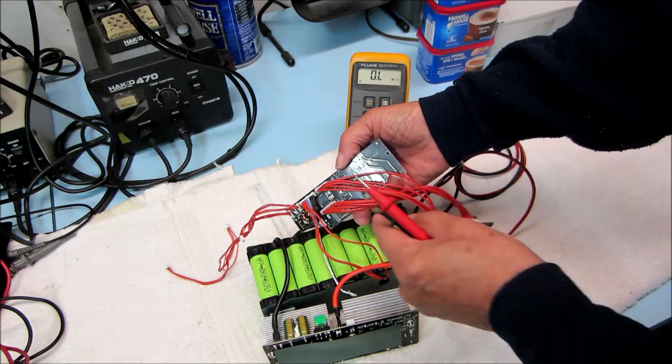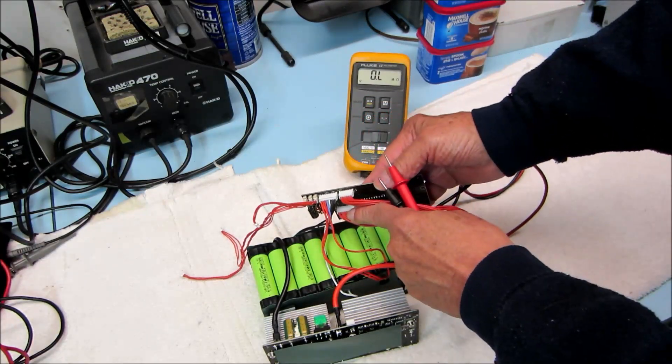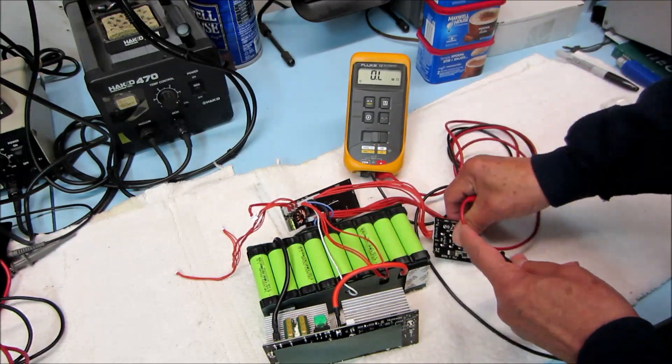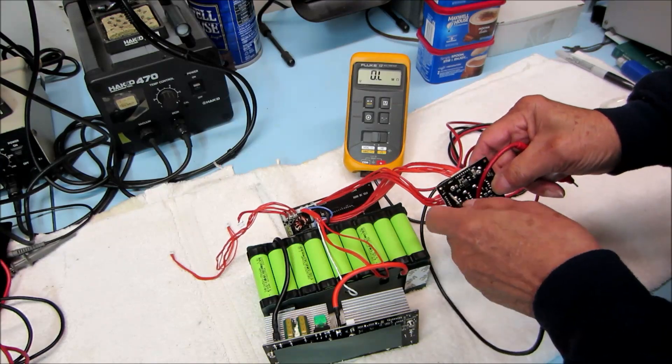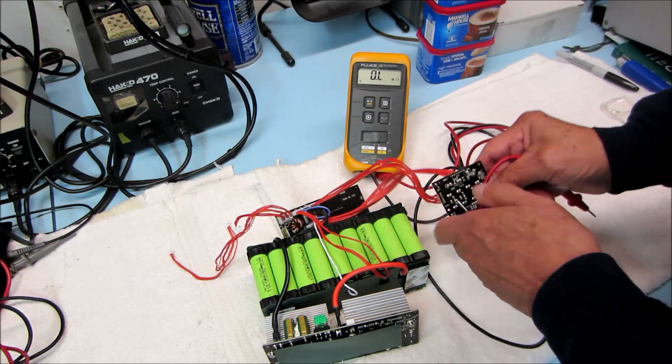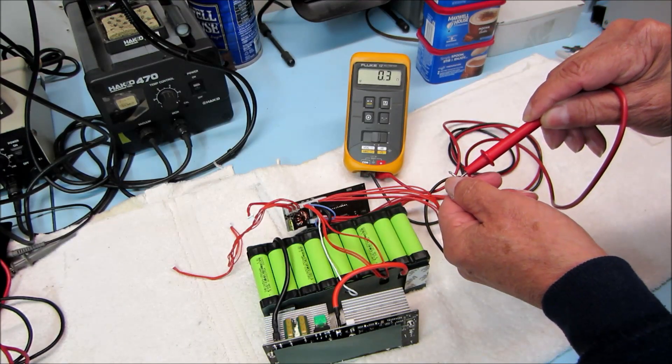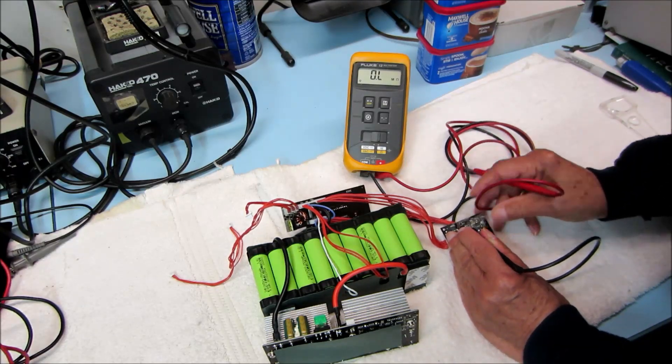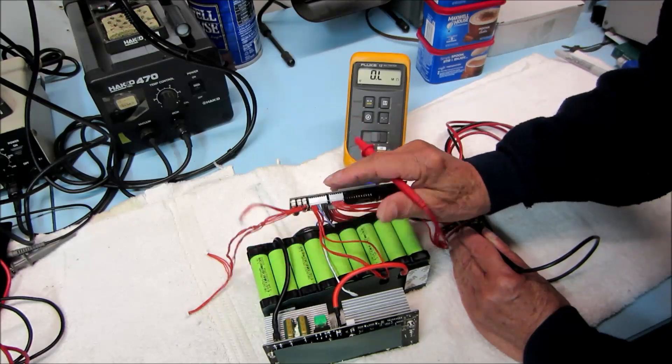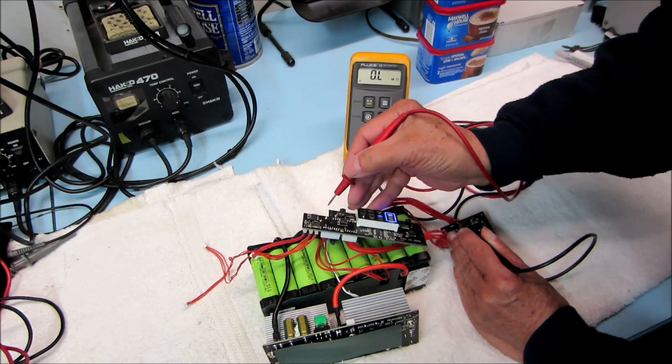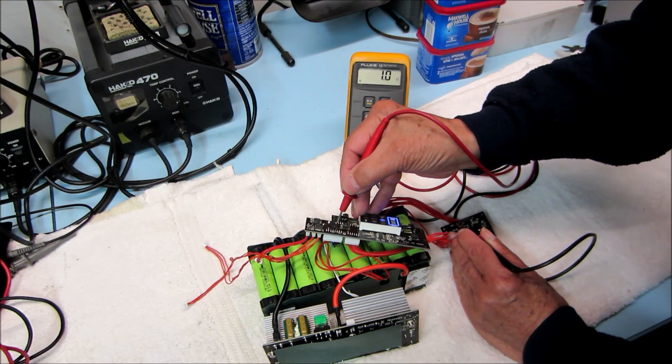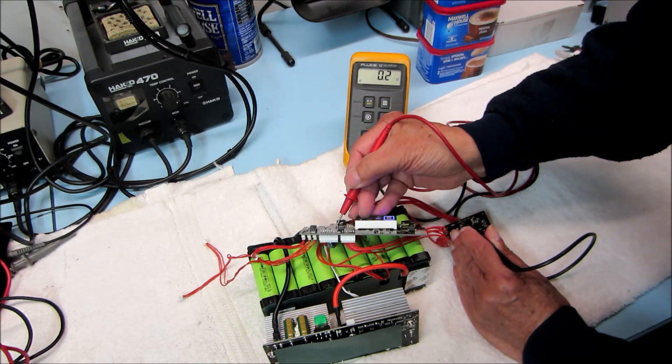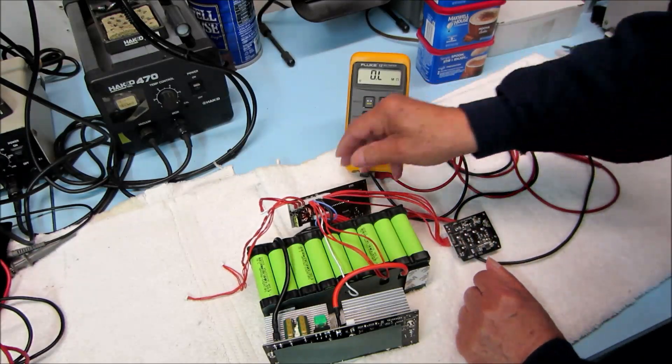And I've already found the negative. I marked it with a black mark. And what you would do, I'm gonna put the probe on the positive connector. First we'll test our meter, so it goes to low ohms, three tenths of an ohm, that's the resistance of the test leads. So I'm going to touch the positive, then you go to this bottom connector. Of course you follow this out by hand. And it works, we have continuity here. We'll do the same for ground. Second pin is working.